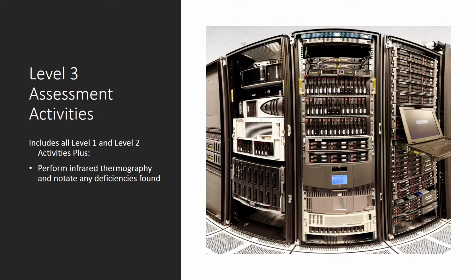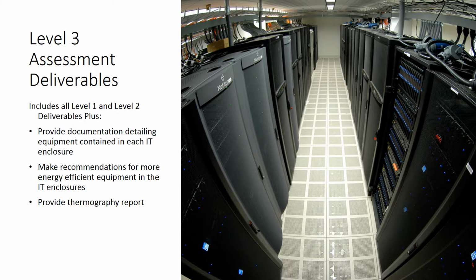During the Level 3 assessment, all of the activities completed during the Level 1 and Level 2 assessments will be completed, including infrared thermography of the space with any found deficiencies being noted. Once the Level 3 assessment is complete, K&A will provide a full deliverable to the customer with all findings. This deliverable will include everything from the Level 1 and Level 2 assessment deliverables, plus the full thermography report. This deliverable will also include any documentation that details the equipment that is contained in each IT enclosure, along with any recommendations for more energy efficient equipment within the IT enclosures.